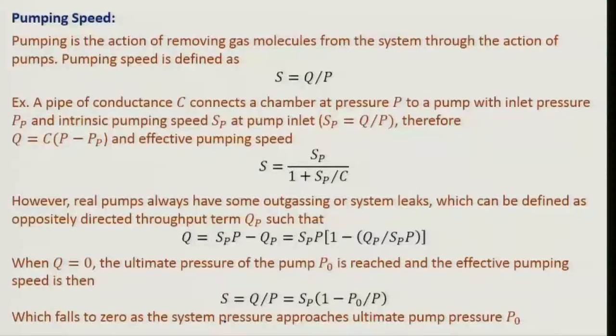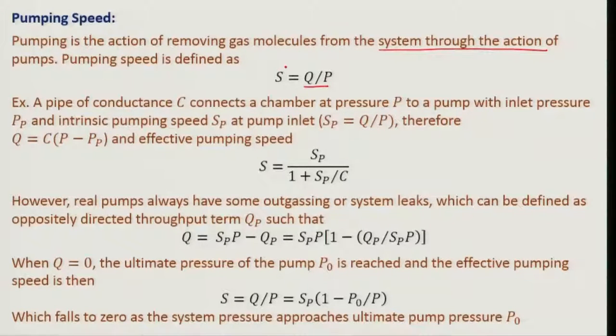To create vacuum, we use some kind of vacuum pump. The vacuum pump's main objective is to remove gas from the vacuum or deposition chamber. The pump is specified by a pumping speed — how much gas it can remove and at what rate. Pumping is the action of removing gas molecules from the system through pumps. Pumping speed S is defined as throughput divided by pressure, and its unit is volume per second.